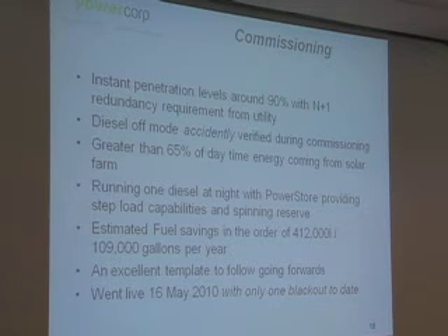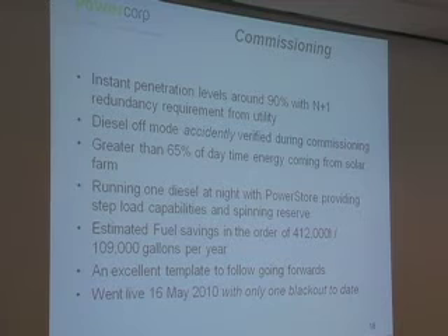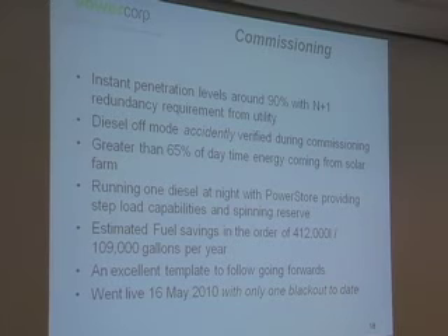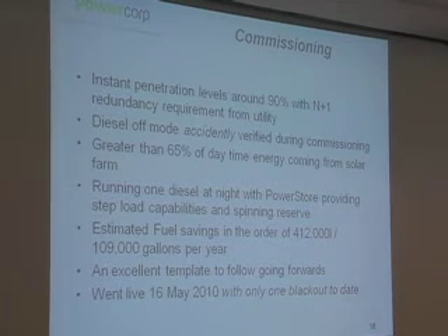So he turned them all off, and we came in and did our step load tests, and all the lights stayed on. We asked to look at the graph of the diesels, and they weren't on—it was just the flywheel and the solar going. So we ran some further tests, and we're happy that the station will be able to run in that diesel-off mode. However, as Russell alluded to earlier, there's the fault current issue that needs to be addressed and worked through with the end customer.